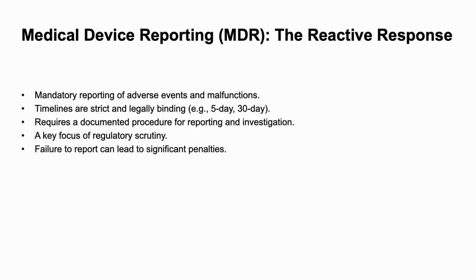Medical device reporting, or MDR, is the reactive and legally mandated process of reporting adverse events and device malfunctions to the relevant regulatory body. For example, in the United States, the FDA requires manufacturers, importers, and device user facilities to report certain adverse events. There are strict and legally binding deadlines for these reports. For instance, a manufacturer must submit a report to the FDA within 5 workdays for a reportable death or serious injury, and within 30 days for a device malfunction that could lead to death or serious injury if it were to recur.